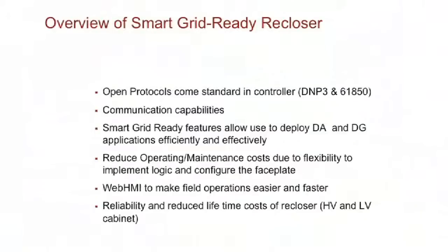And some of the benefits, for example, the cold load logic that comes default with our relay might not be exactly the way you handle it. So if you need to change your operation procedures because our logic is a certain way, that obviously has an impact on your operations. So we can sit down and program the logic to match what you're already using. And again, it helps you reduce those costs of, now I'm putting something new that I know is great because it's going to allow me to deploy a lot of smart grid applications, but it's now hard for my operators to use. So these are some of the three things that we put into the design to make it, again, easy for the operators to use and address some of the issues that you're having. On top of being worried about the new emerging technologies that you need to support, you're always going to have to worry about cost, right? And operational efficiencies, how easy it is for your operators to use the equipment.